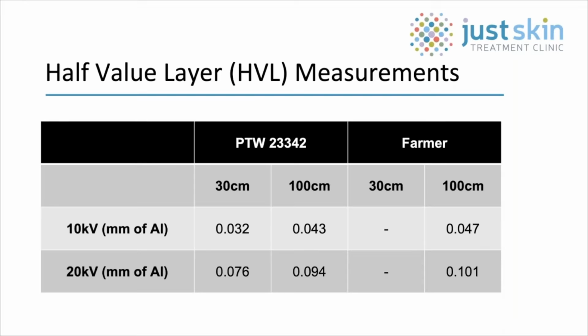These are the HVL values from the latest machine I've commissioned for Grenz. You can see a pretty significant variation between the 30 centimeter and 100 centimeter measurement. If you decide to only use the 100 centimeter HVL, the effect on the final dosimetry in my case would have only been 0.2% for the 10 kV beam, so it's not particularly significant.